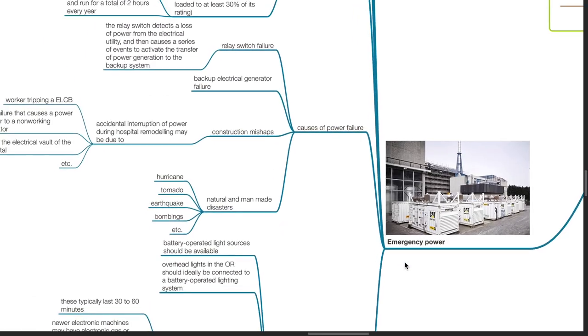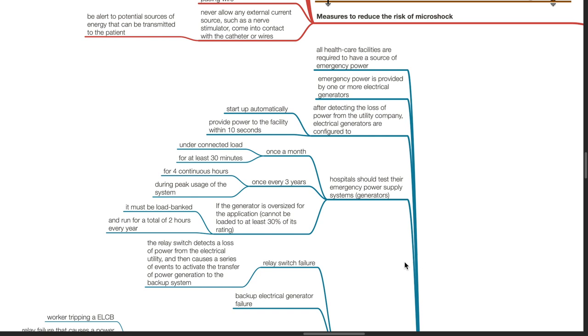Emergency power. All healthcare facilities are required to have a source of emergency power provided by one or more electrical generators. After detecting the loss of power from the utility company, electrical generators are configured to start up automatically and provide power to the facility within 10 seconds. Hospitals should test their emergency power supply systems and generators once a month under connected load for at least 30 minutes, once every three years for four continuous hours during peak usage of the system. If the generator is oversized for the application and cannot be loaded to at least 30% of its rating, it must be load banked and run for a total of two hours every year.